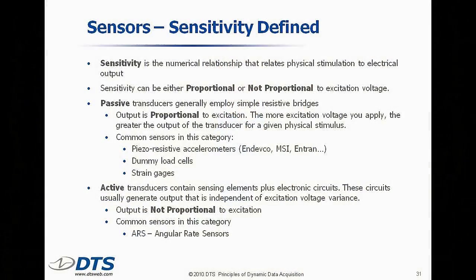But these things actually put out an output voltage that's very high level, and they have circuits as well as sensors inside. Okay, sensitivity. The most important thing you need to have a good handle on when it comes to setting up a transducer. Sensitivity is the numerical relationship that relates the physical stimulation to the electrical output. That means if I put X number of pounds, newtons, Gs, I get this amount of voltage out of it. That's simply put what it is. It relates the physical input to the electrical output.